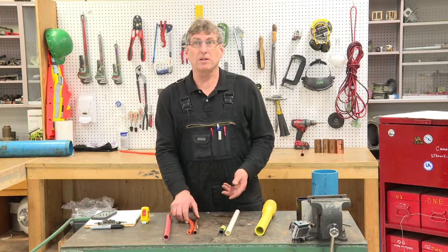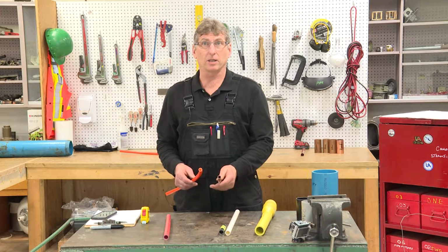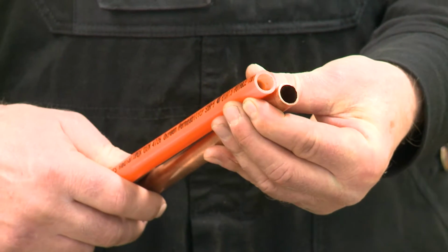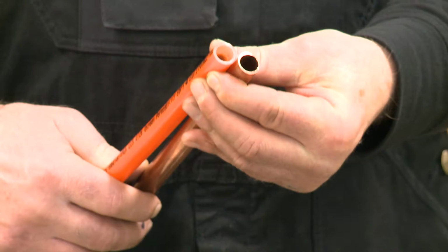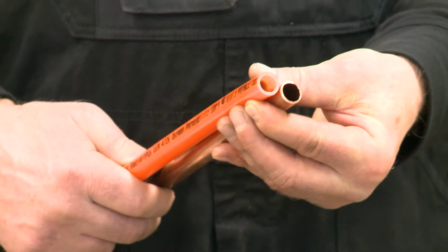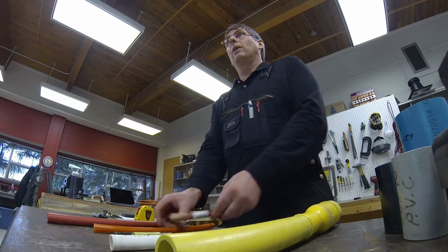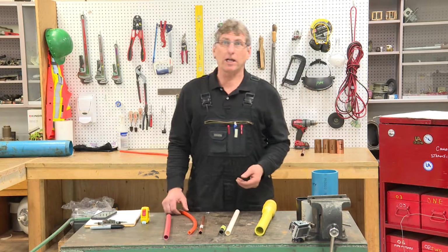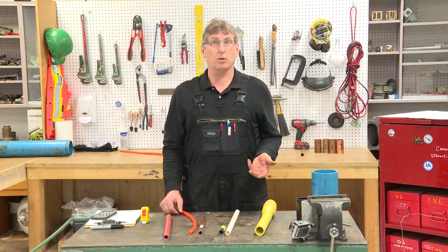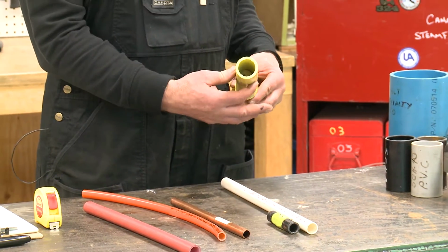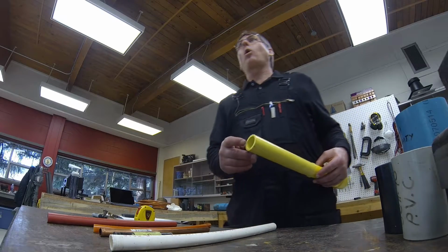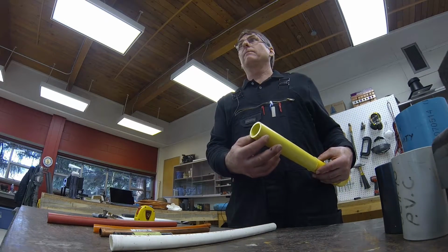Look closely at this piece of half-inch CTS PEX tubing. You see it has the same outside diameter as half-inch CTS copper tube, but the wall thickness for the PEX needs to be much thicker than the copper tube to get the necessary pressure rating. So, SDR ratings. It's actually a pretty straightforward system. SDR is the ratio of the outside diameter divided by the wall thickness. Or in other words, how many times does the wall thickness divide into the OD?